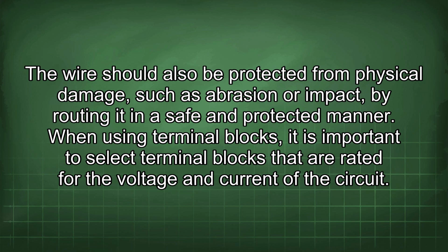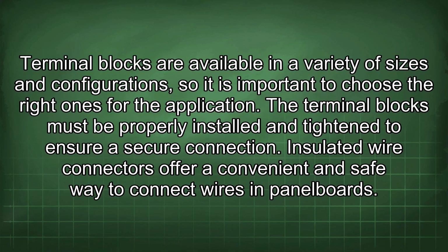When using terminal blocks, it is important to select terminal blocks that are rated for the voltage and current of the circuit. Terminal blocks are available in a variety of sizes and configurations, so it is important to choose the right ones for the application. Terminal blocks must be properly installed and tightened to ensure a secure connection. Insulated wire connectors offer a convenient and safe way to connect wires in panel boards.